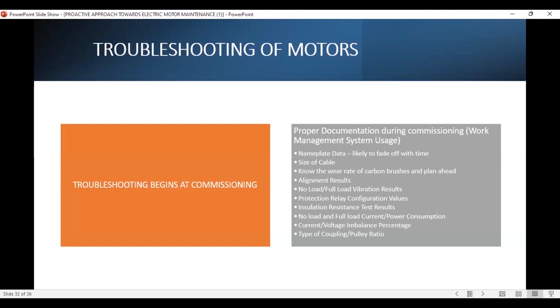After the motor has been installed, the alignment has to be done and the results have to be kept so that for future reference, you know what the alignment was. So every three months, you check your alignment, you ensure there is no deviation, and where there is deviation, you correct it and you allow your motors to run in good shape. And no load and full load vibration results must also be taken during commissioning. So you know your motor is operating rightly, or the equipment your motor is driving also has an issue. You have your data and you keep it for future analysis.